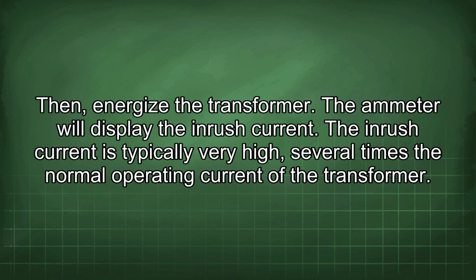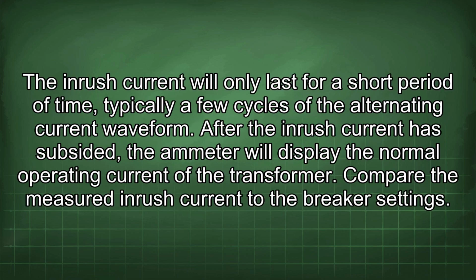The inrush current is typically very high, several times the normal operating current of the transformer. The inrush current will only last for a short period of time, typically a few cycles of the alternating current waveform. After the inrush current has subsided, the ammeter will display the normal operating current of the transformer.